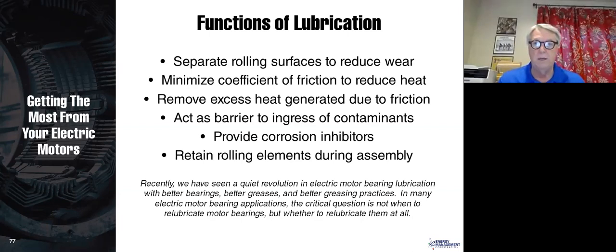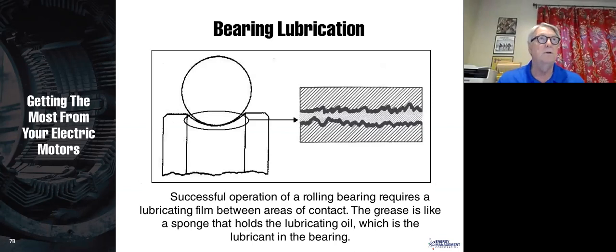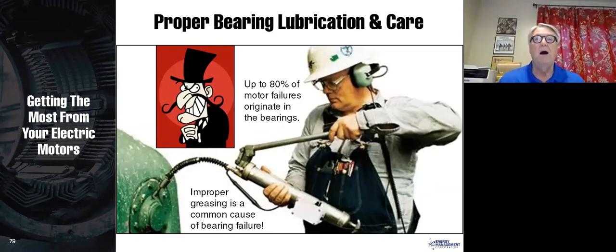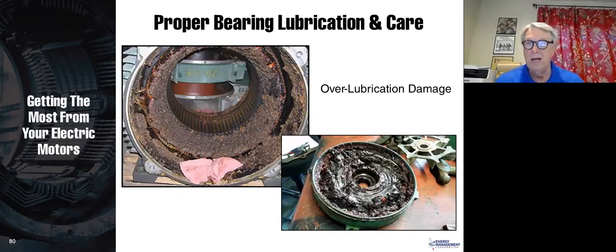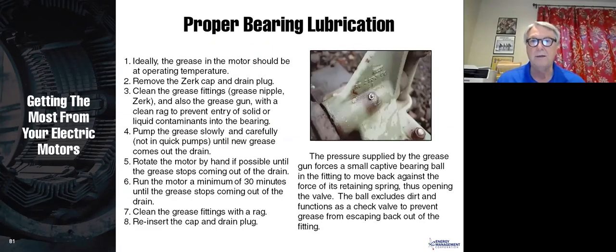So I'm not going to spend a lot of time with that because I want to talk about some more interesting things. You notice that even though the races look smooth, they're not terribly smooth, and so you need a lubricating film. Up to 80% of motor failures originate in the bearing, and improper greasing is a common cause of bearing failure. So that's what I want to talk about, is how to grease a motor. You might guess that these motors have been improperly greased. If that's your guess, you would be correct. Now let's talk about how to grease a motor.